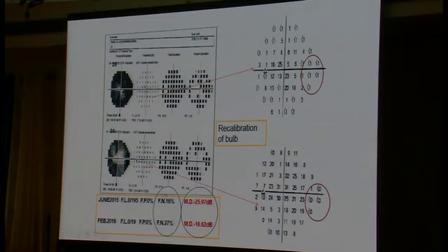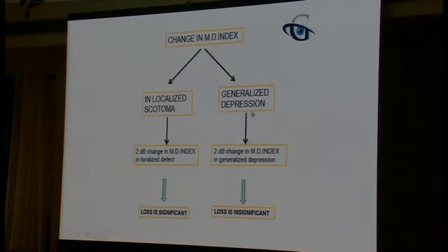If you see the reason, normally an inferior sign should appear in front of a 0. That means this point is not responding to the maximum light intensity. And if the light intensity is not 10,000 ASB units, an inferior sign appears in front of a numerical value. That itself is an indication for recalibration.